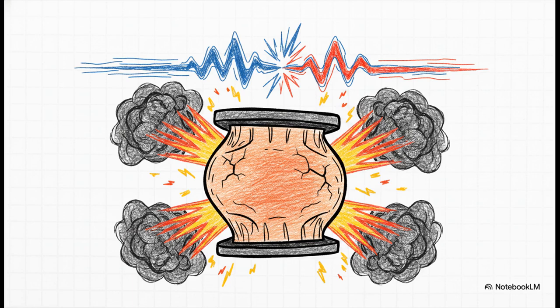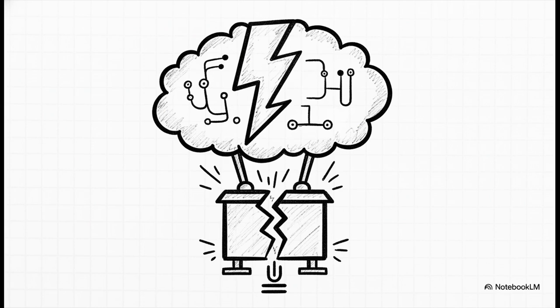Rule 5 is simple, but it is absolute. Never use a 60 Hz rated VT on a 50 Hz system. It's a bad idea. A frequency mismatch leads to the internal core saturating much faster. This leads to severe overheating. And if you try to run a 60 Hz VT at 50 Hz, severe equipment failure isn't just possible, it's highly likely. Finally, we have Rule 6.